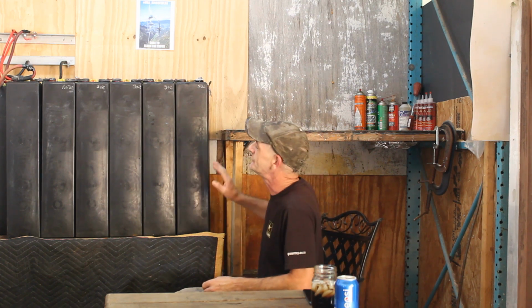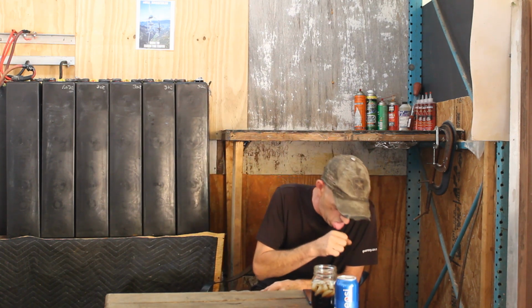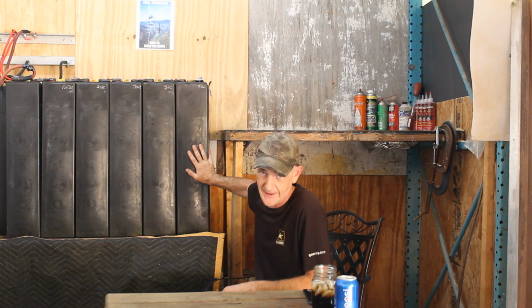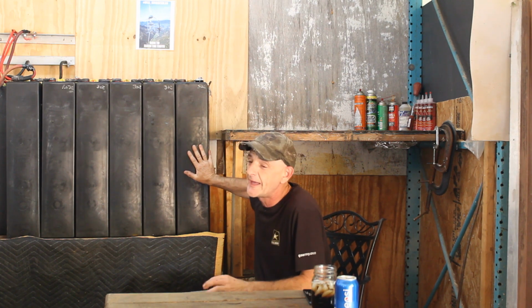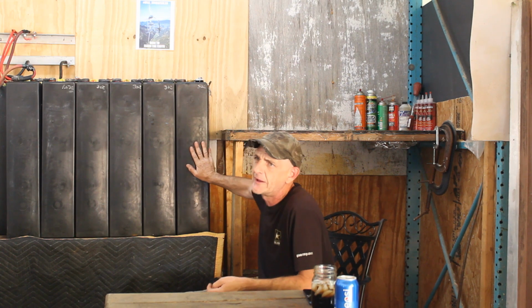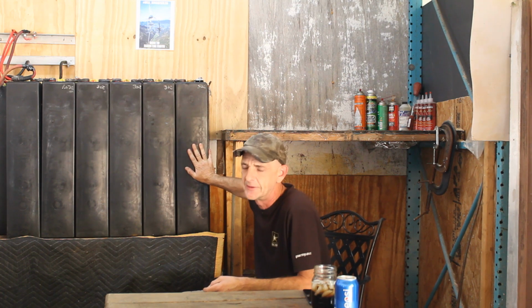Yeah, this is another great thing about IFLAs. These things are rated at a C6 rating. Okay? What that means is, take your amp hours, divide it by 6. That battery will provide you that many amps for 6 hours. I believe these are 800, so I think 133 amps for 6 hours is what the 6-hour rate is on these.